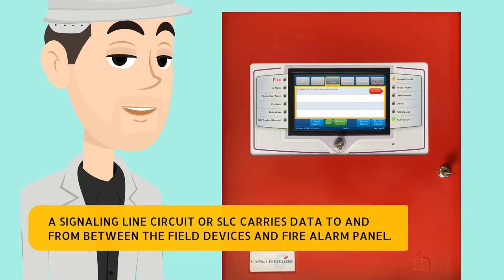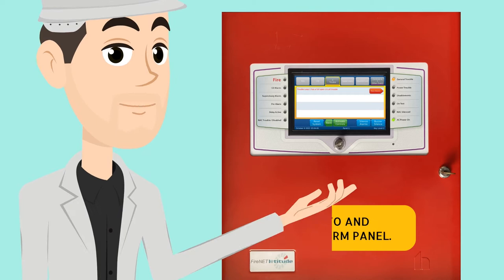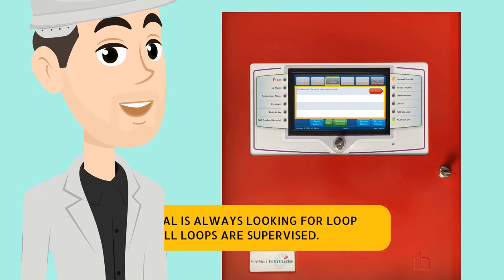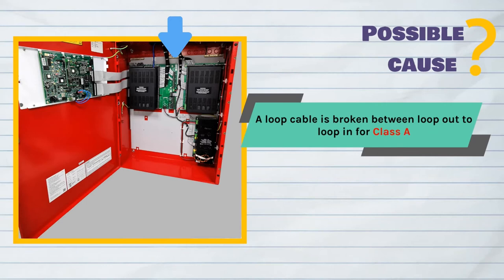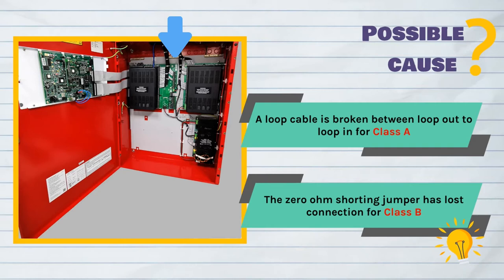A signaling line circuit, or SLC, carries data to and from between the field devices and the fire alarm panel. The SLC loop in terminal is always looking for the loop out terminal — all loops are supervised. The possible cause of loop open circuit trouble is either a loop cable is broken between loop out to loop in for class A, or the 0 ohm shorting jumper has lost connection for class B.